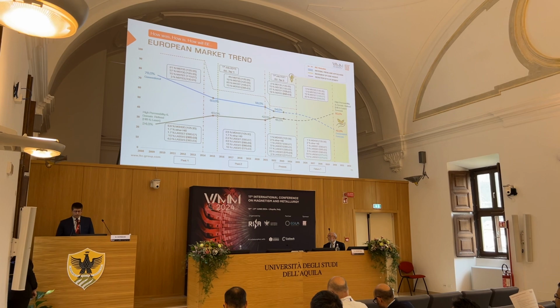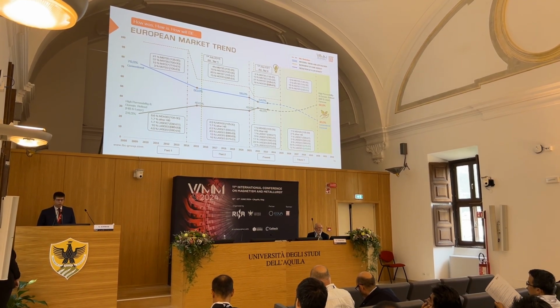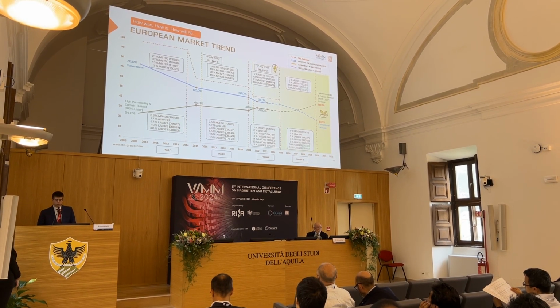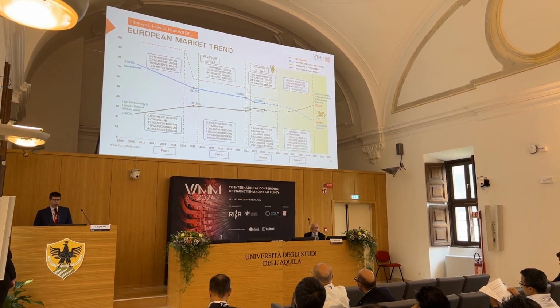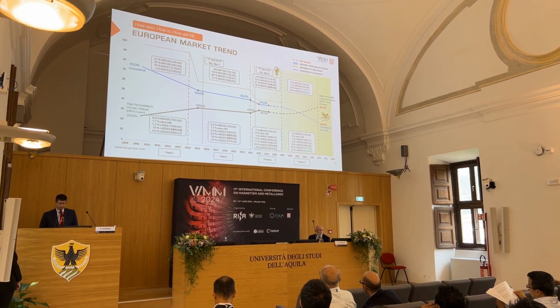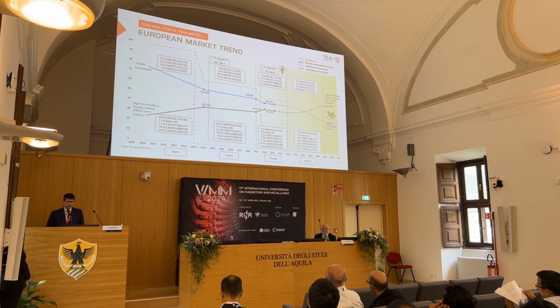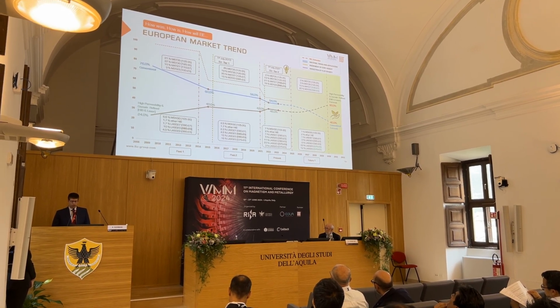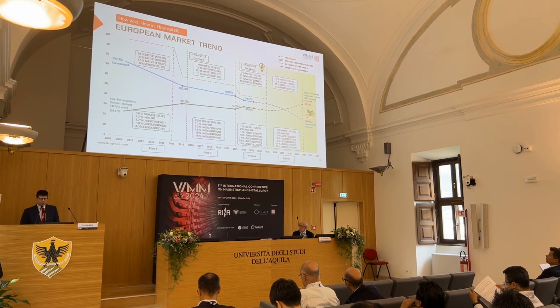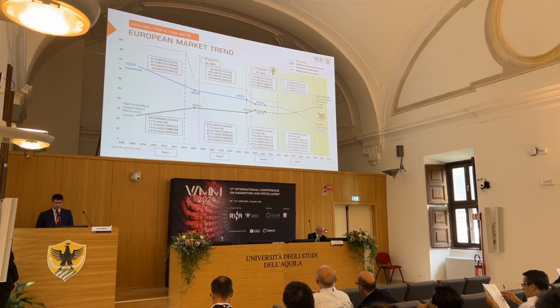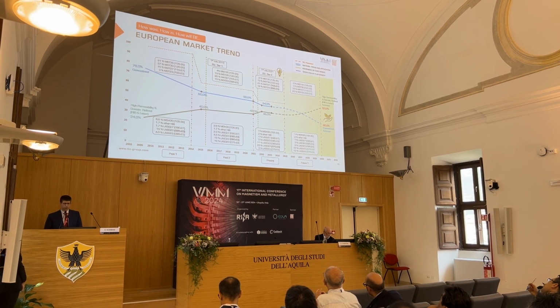And moving ahead in the future, we can see the trend is always to reduce the no-load loss. So the trend is moving in the direction of having more and more high permeability and laser-treated material. And we can expect by 2030 that the demand and the consumption will be 60% in the laser and high permeability material and only 40% in the conventional.